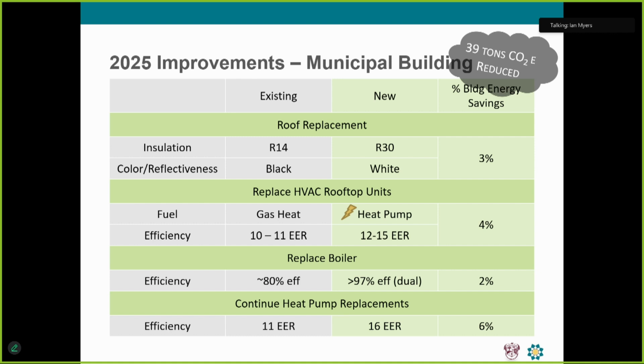It's why we have this push for electrification. It's why heat pumps fit in nicely with solar projects and other sorts of sustainability efforts, is that combustion equipment is never going to be able to do that. Combustion equipment, even at its best, is approaching a coefficient of performance of 1. But with heat pumps, we can have a coefficient of performance of 3, 4, 5. They're even getting up to 6. And so to be able to be 6 times more efficient and using electricity, removing fossil fuels from the building, it really ties into all the other sustainability efforts that you're also trying to achieve.